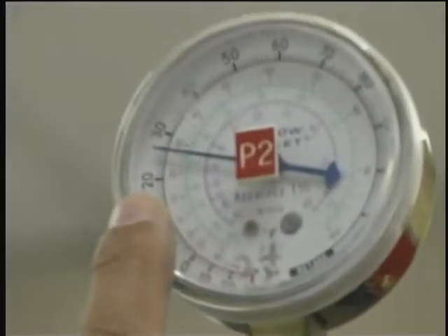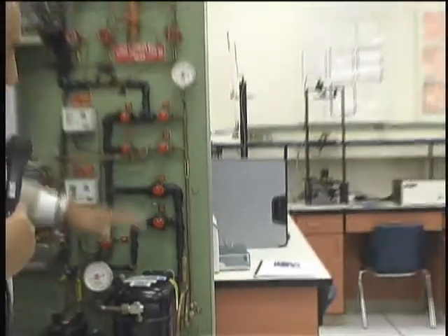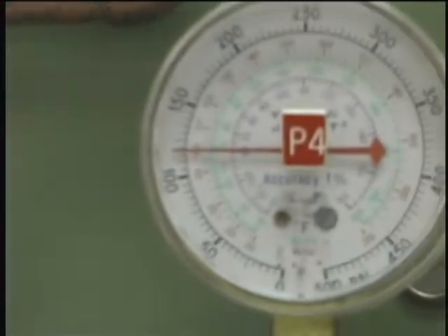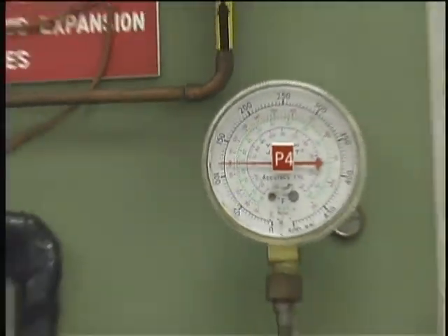You can see now that the pressure up here is like 20-some, and the pressure at the intake of the compressor is now down to about 12 or 13. And the compressor has done work, and it increases the pressure to about 120. So it's doing the right thing. But it's still kind of in a transient state, and it's going down. If you just put your hand, you'll feel that it's cold here, and it starts to warm up here.